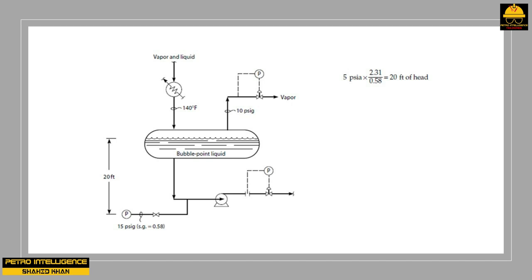Unfortunately, the drum is already almost full. Suppose we instead increase pressure by partly closing the back pressure control valve, quickly increasing drum pressure from 10 to 15 PSI G and pump suction pressure from 15 to 20 PSI G. This does not provide more NPSH, because as the pressure in the drum increases, additional lighter components dissolve in the liquid, making the liquid composition lighter.